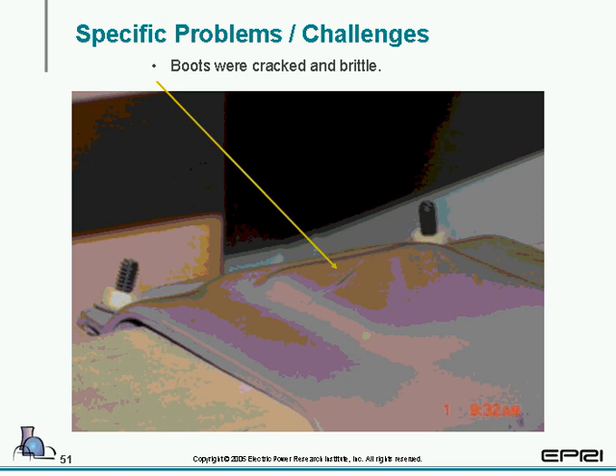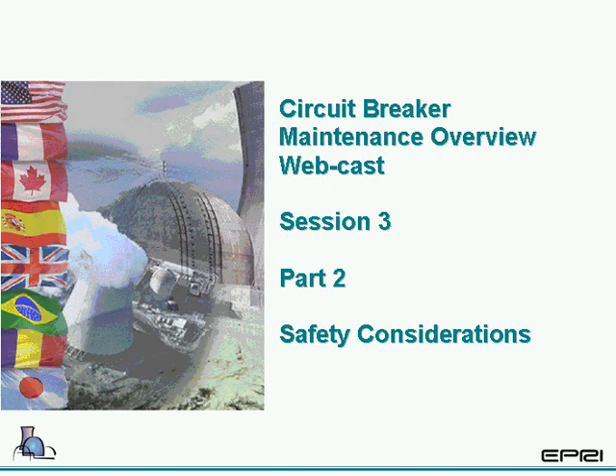And the last thing we saw with specific problems was that any of the boots, rubber, nylon parts had cracks, splits, or when they were being removed or taken apart, would fall apart or break. And that also went to the insulation of the cables: as you pulled them off of the bus, the actual insulation would split and crack. It was brittle as well. And that ends specific problems and challenges with the cubicle and breaker.